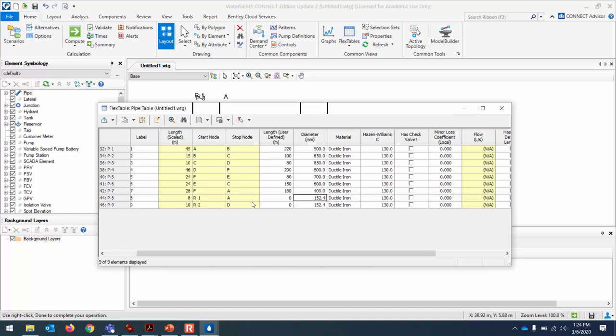These virtual pipes ensure a certain pressure at A and at junction D. You won't need to do this in your design project — all pipes there will be real. Now the material shows ductile iron, but we need to change it to cast iron. Use the drop-down material library: cast iron has a roughness height of 0.0003 meters (0.3 millimeters), matching the epsilon value from the Excel example. To change all pipes at once, right-click at the top of the list, select global edit, and type cast iron.